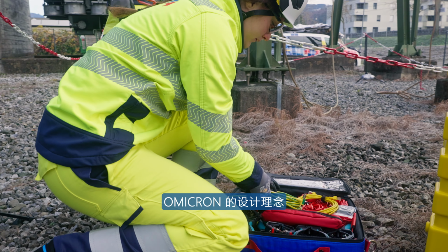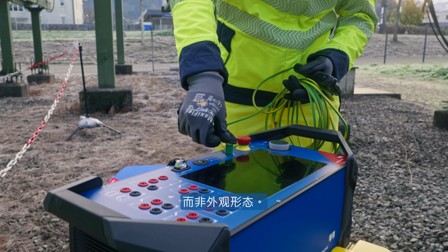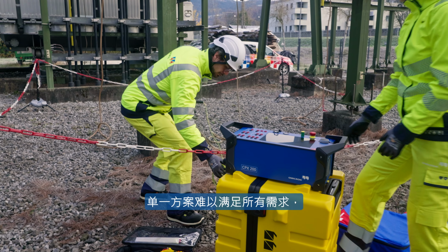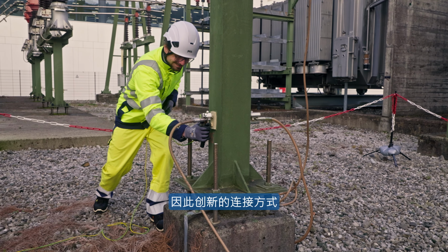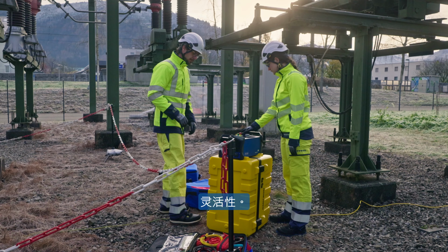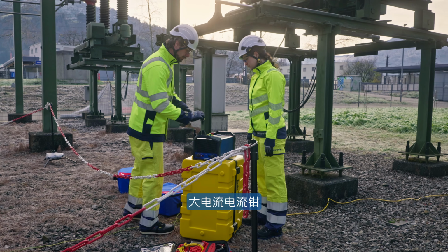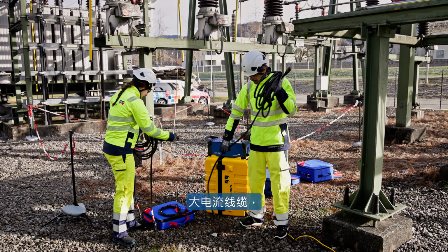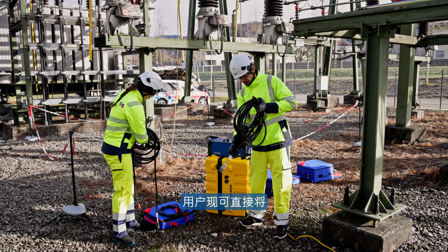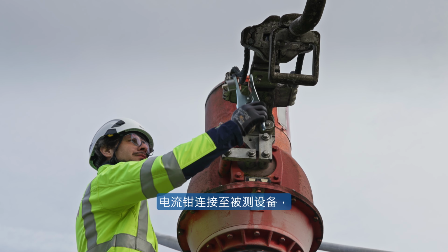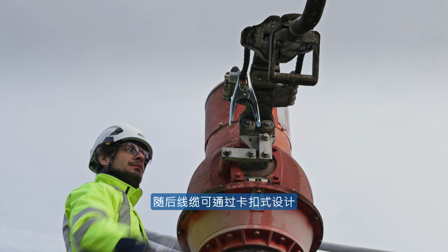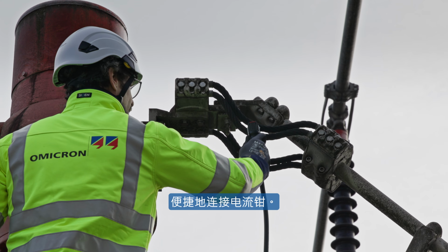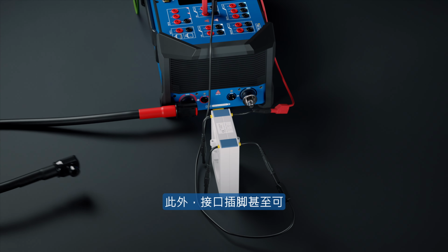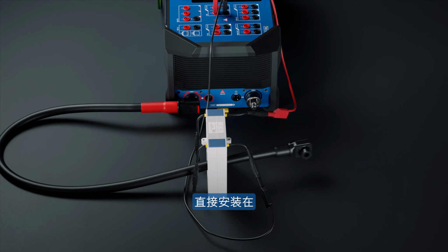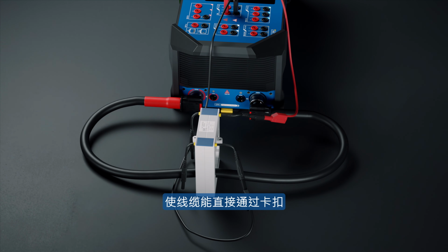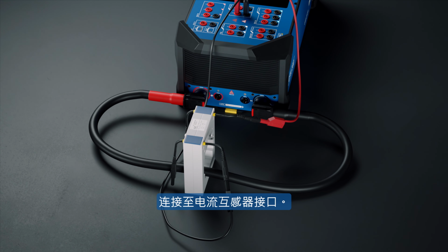At OMICRON, design is more about how things work than how things look. We recognize that one size doesn't fit all, and our new connection method provides users with the flexibility they need. The high current clamp is not directly connected to the high current cable anymore, which now allows the user to connect the clamp directly to the asset. Afterwards, the cable can then be conveniently snapped onto the clamp. Alternatively, the connector pins can even be mounted directly to the connector of the CT, allowing the cable to then be directly snapped onto the CT connector.